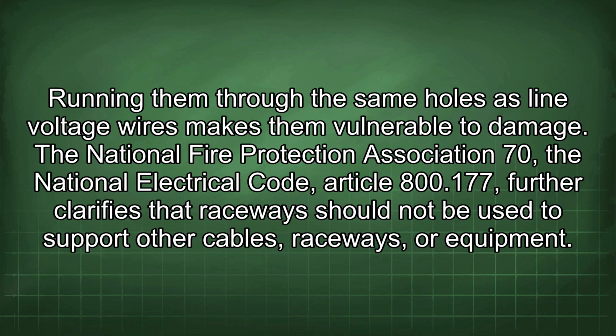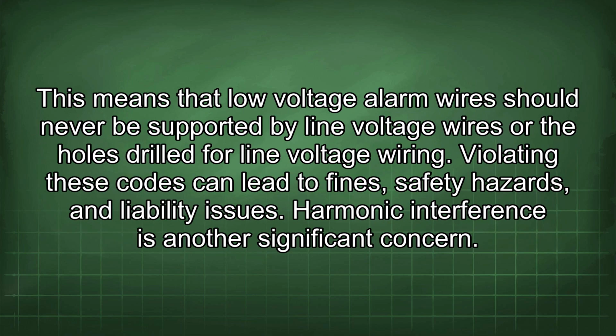The National Fire Protection Association 70, the National Electrical Code, Article 800.177, further clarifies that raceways should not be used to support other cables, raceways, or equipment. This means that low voltage alarm wires should never be supported by line voltage wires or the holes drilled for line voltage wiring. Violating these codes can lead to fines, safety hazards, and liability issues.